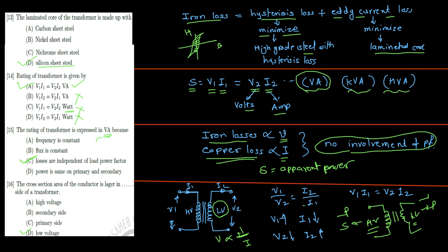because current and voltage are inversely proportional. So V and I are inversely proportional in case of a transformer. See, Ohm's law says that it is directly proportional, but in a transformer voltage and current are inversely proportional. So in the low voltage winding the current is higher, in the high voltage winding the current is lower. So a larger cross section area will be required where the current rating is higher. So which current rating is higher? Low voltage winding current rating is higher. So don't give the answer primary or secondary, because primary or secondary may be the low voltage winding or maybe the high voltage winding. Okay, so let me launch the next question.